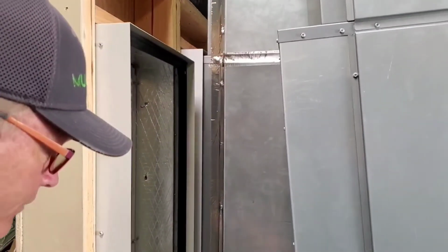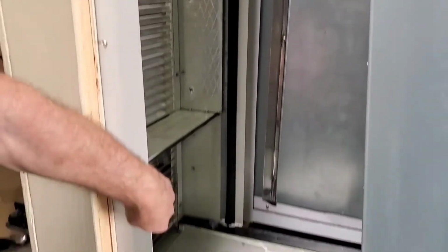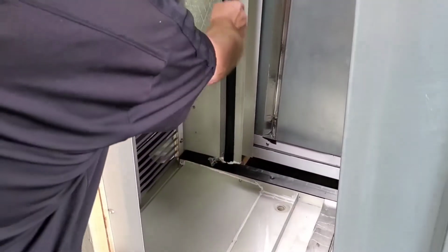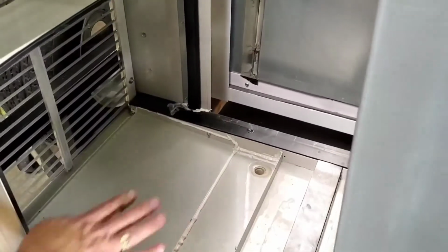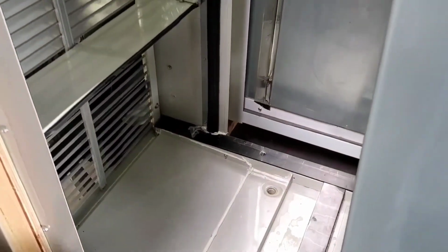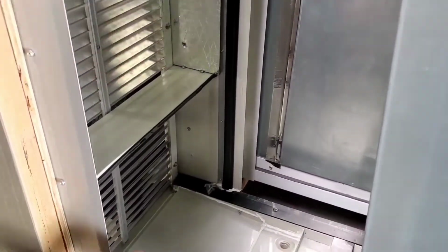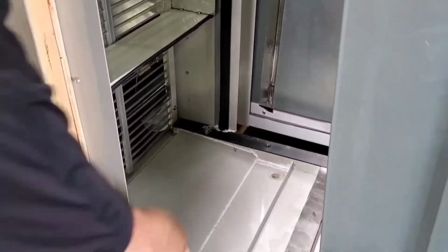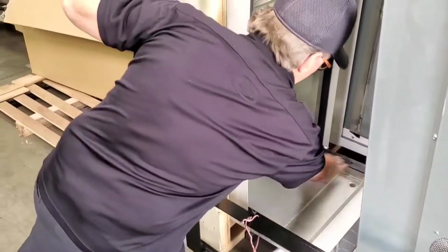When you slide the unit out, you're going to see the same platform through the wall sleeve. Check the gasket all the way around to make sure that it's in good shape, no rips and tears. And down here at the bottom, you're going to have a plastic coated rubber seal. If you don't have a good plastic coat on this, get some clear tape and put it on there so you have a good sliding plastic over top of the rubber.